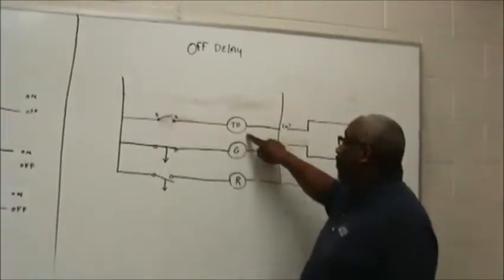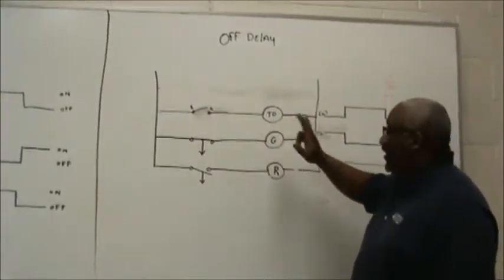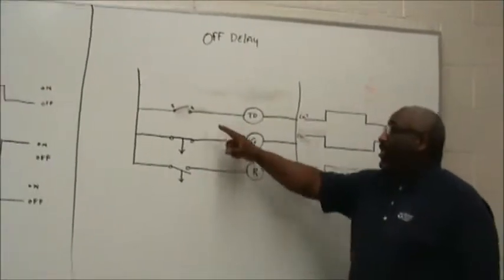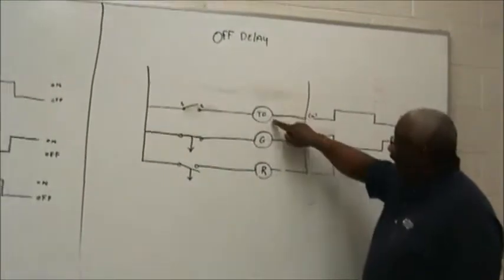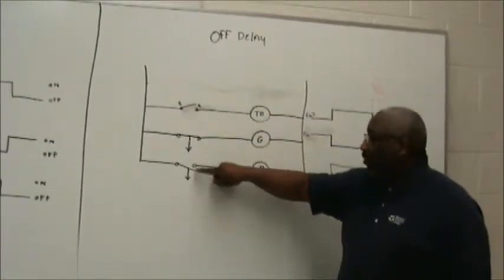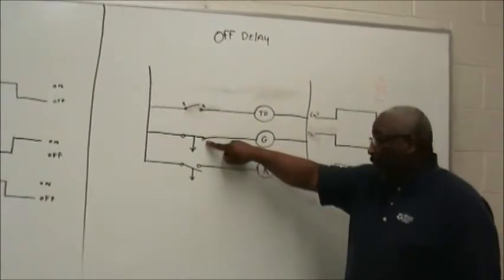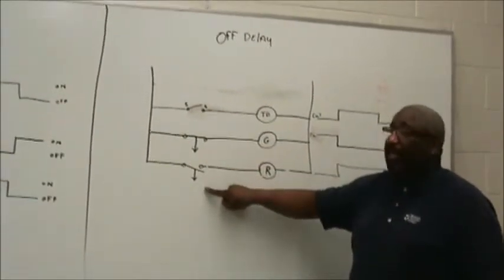Again, a switch is controlling the timer coil. When I say it's instantaneous, I'm saying at the time that you energize this coil, the contacts will change their state. The closed will immediately go open, and the open will immediately go closed.